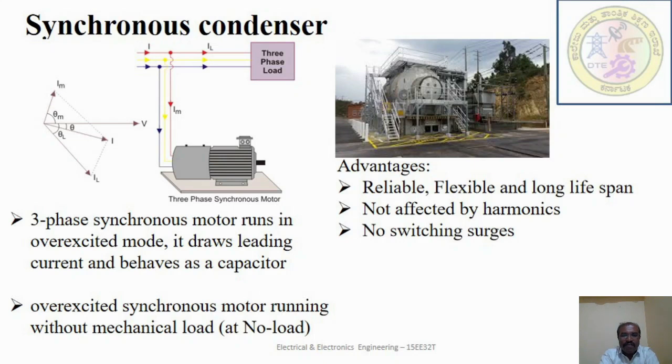You can observe in a waveform the power factor is increased from cos phi L, that means phi L the angle, to phi, because it is an inductive load. Current lags the voltage by some angle, that is phi L. The V is lagged by the load current IL by the angle phi L. By connecting the synchronous condenser, the angle is reduced. That means the current I is shifted, and the power factor is increased from cos phi L to cos phi.